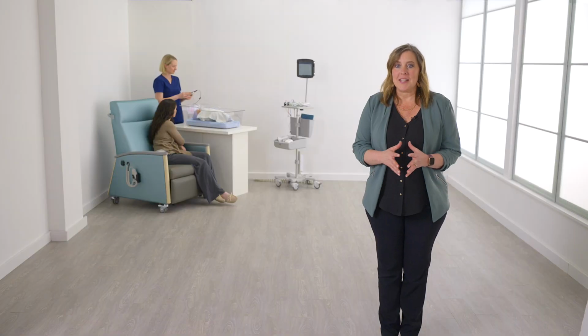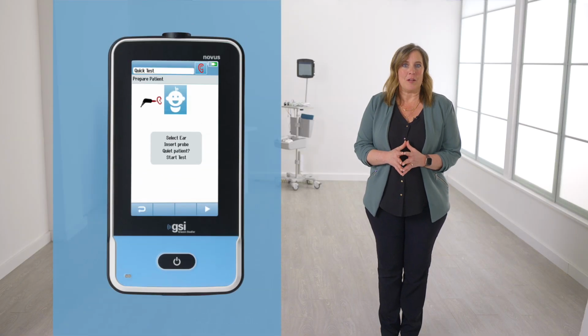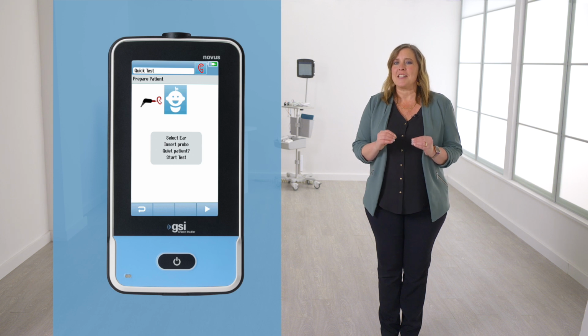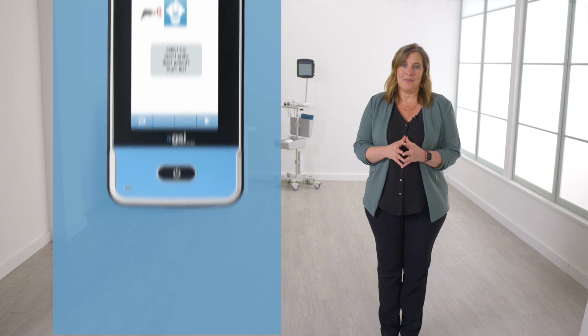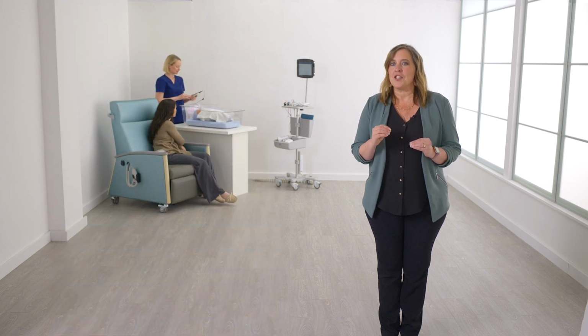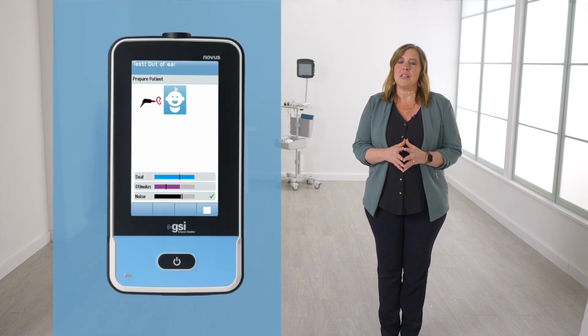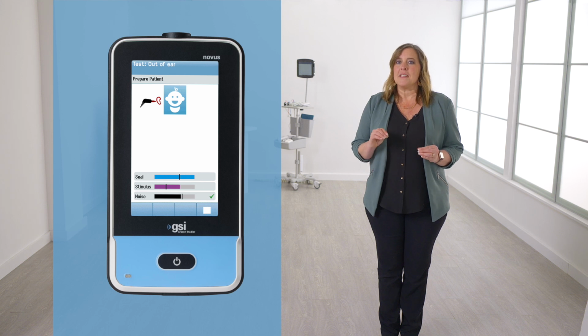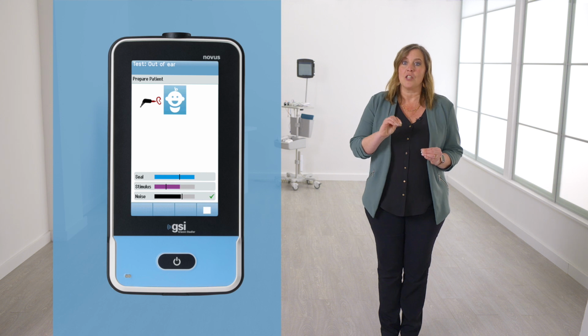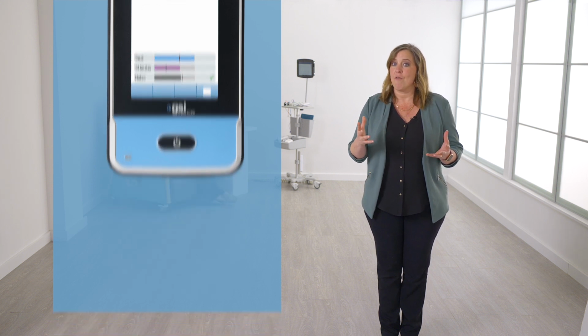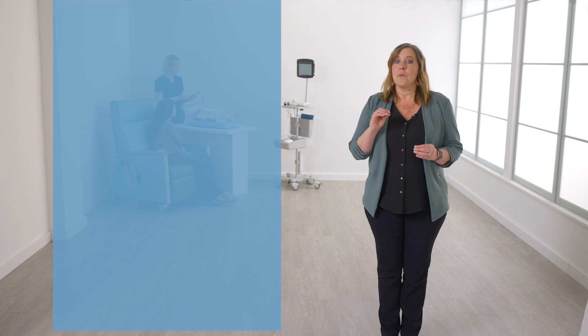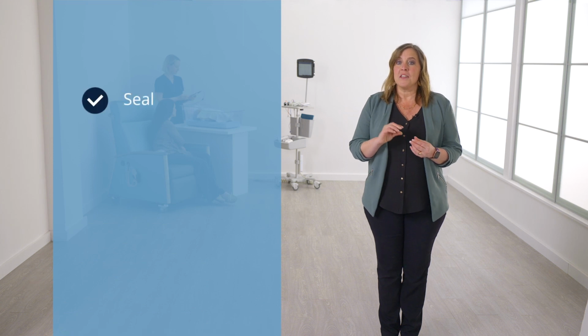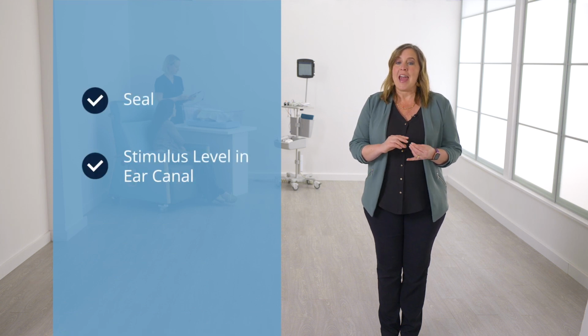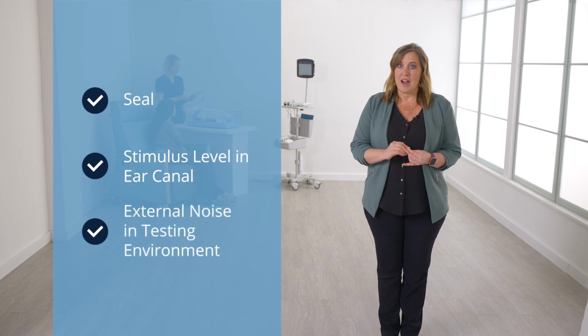Once the patient name is selected, the initial test prep screen will appear. Take a couple of seconds to verify the patient's name and ensure the appropriate ear is selected. When the probe is placed into the patient's ear, press the Start button to initiate the probe check. This step automatically evaluates the quality of the probe fit in the ear canal to ensure a quality fit and therefore a reliable test. The probe check verifies the seal, the stimulus level in the ear canal, and the external noise in the testing environment.